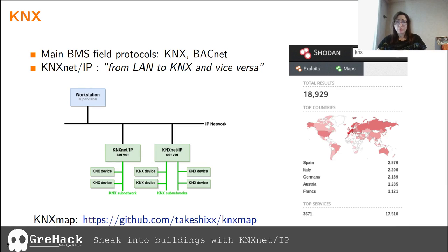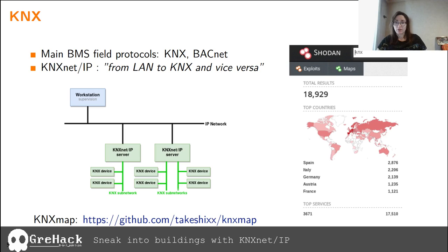Let's talk about KNX. This is a common fieldbus protocol for BMS for both industry and domestic use. Not the most common one, as there is BACnet, but still widely used, especially in Europe. As you can see in this screenshot from Shodan, we can find a lot of devices exposing port 3671, which is the port for KNXnet/IP, the protocol specification for KNX over IP. KNXnet/IP allows interfacing from LAN to KNX and vice versa.